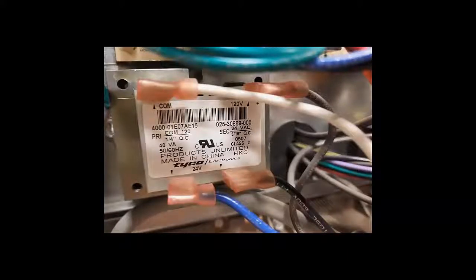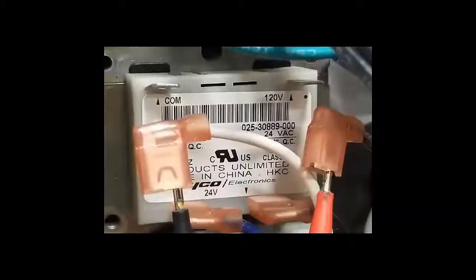All you have to do is pull the line voltage wires off the transformer. Now, make certain the main power is turned off before you do this. Then connect your voltmeter leads to the wires that were connected to the transformer and turn the power to the unit back on. If you get a reading of 110 to 120 volts, plus or minus 5%, you know you have correct voltage to it.